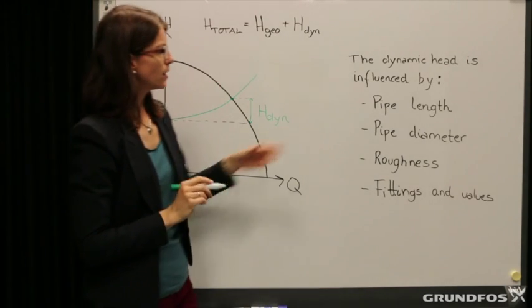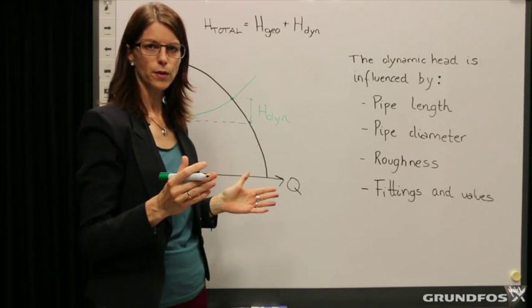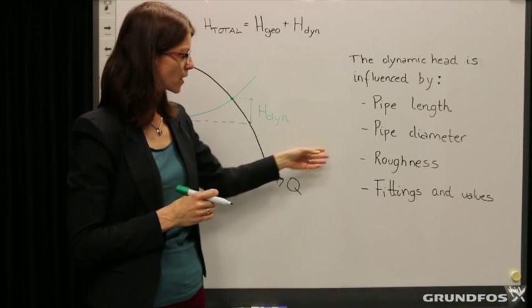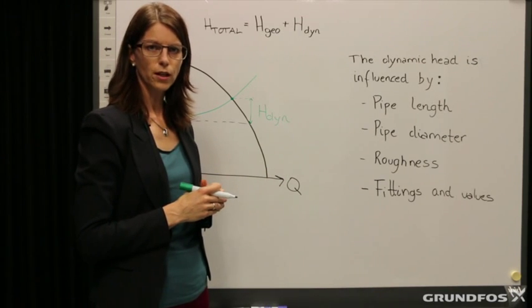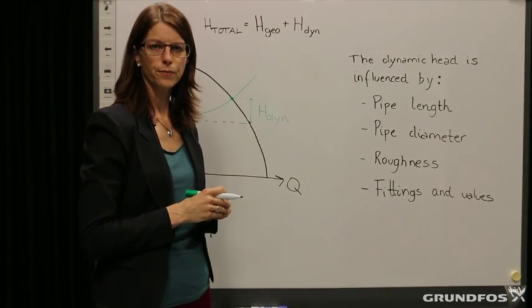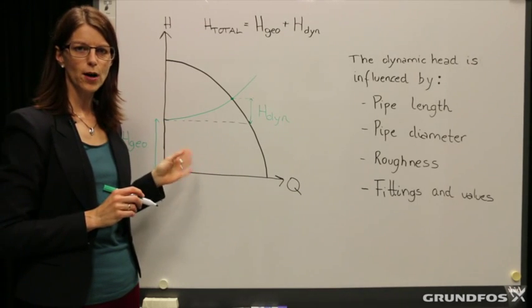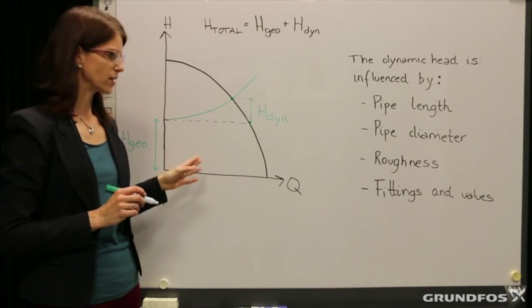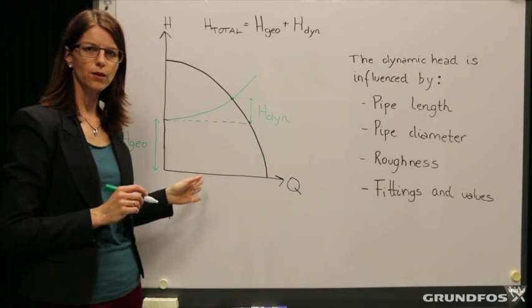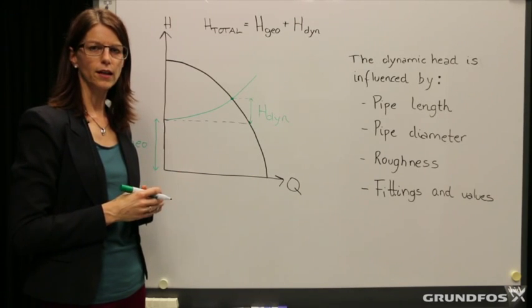The dynamic head is influenced by the length of the pipe between the pump and the sewage mains, the diameter of the pipe selected, the roughness of the surface of the inner pipe, and the fittings and valves mounted on the pipeline. The reason why the dynamic head varies according to the flow is due to the resistance in the pipe depending on the flow velocity. We will look more into that later in this video.